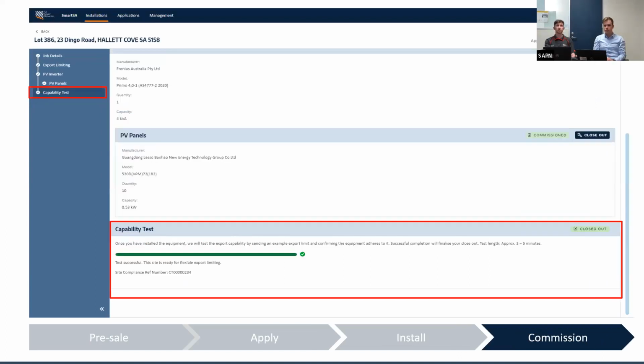Moving on to what hopefully we'll see on all systems: a successful capability test. You can see it's gone to a green closed-out status, with a test successful message underneath, and everything ticked off. You'll also have the site compliance reference number at the bottom of the page. The final check is the status in the top right-hand corner changing to commissioned.